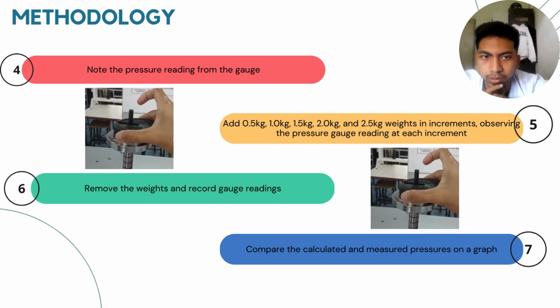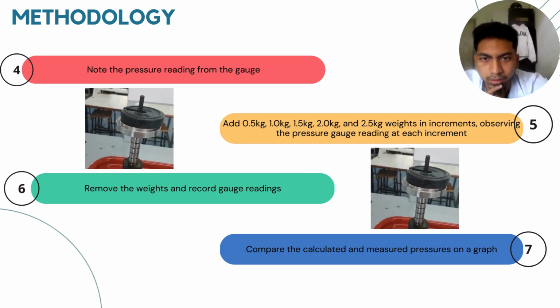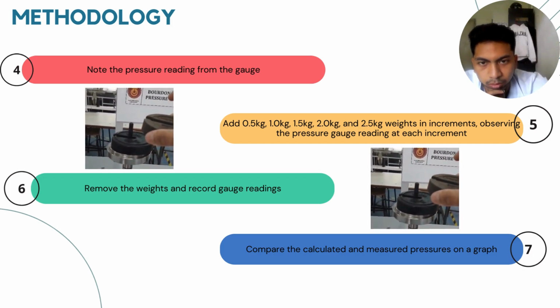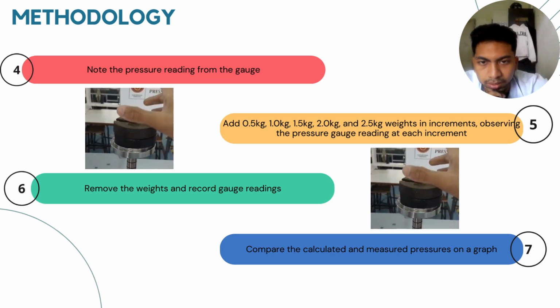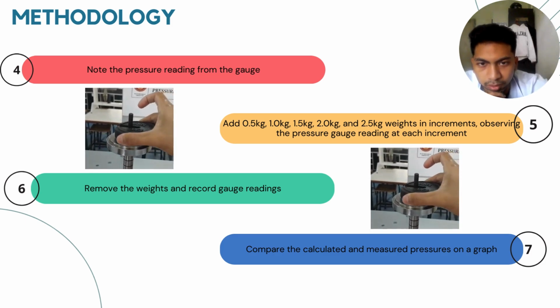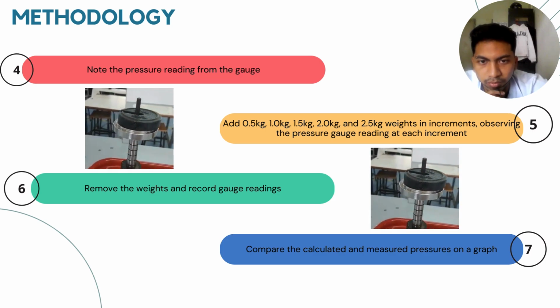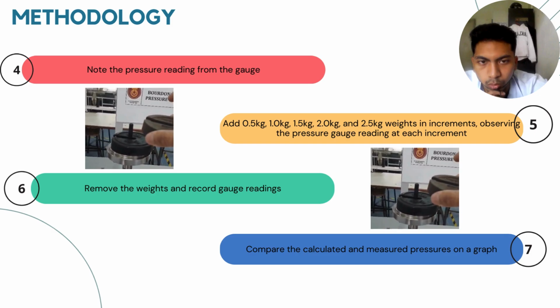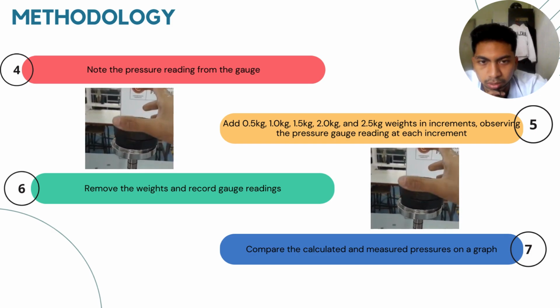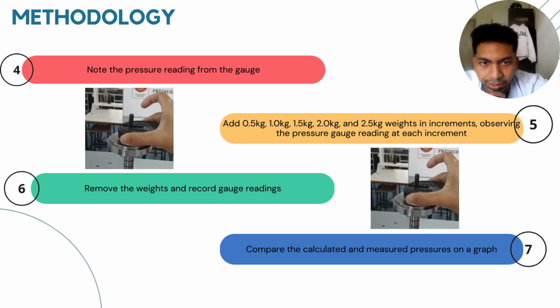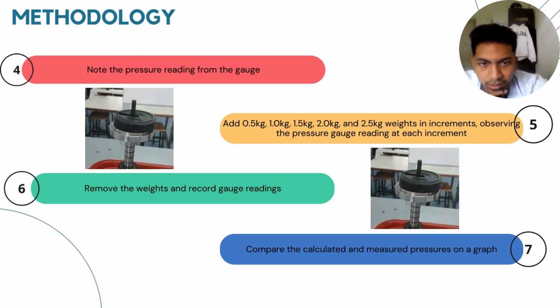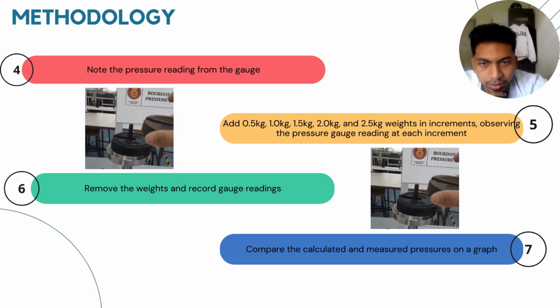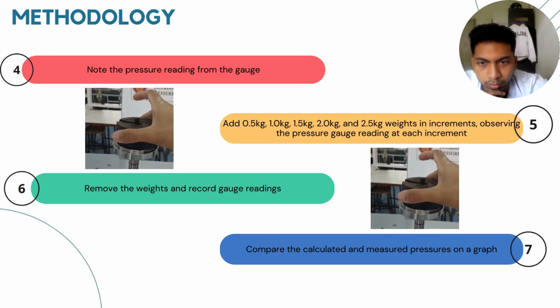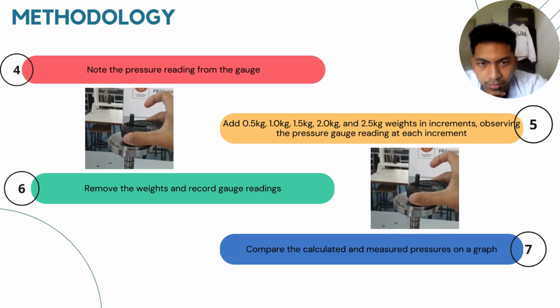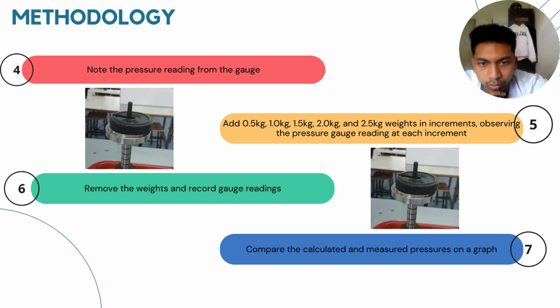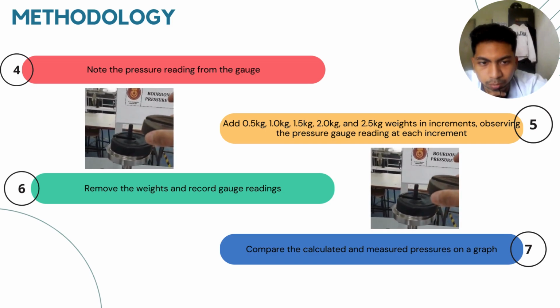The next step is to note the pressure reading from the gauge with the piston at 0 kilogram, and next add 0.5 kilo, 1.0 kilo, 1.5 kilo, 2.0 kilo, and 2.5 kilo weight in increments, observing the pressure gauge reading at each increment. After all the load has been put on the piston, we must remove the weight and record the gauge reading. After that, we must compare the calculated and measured pressure on the graph.